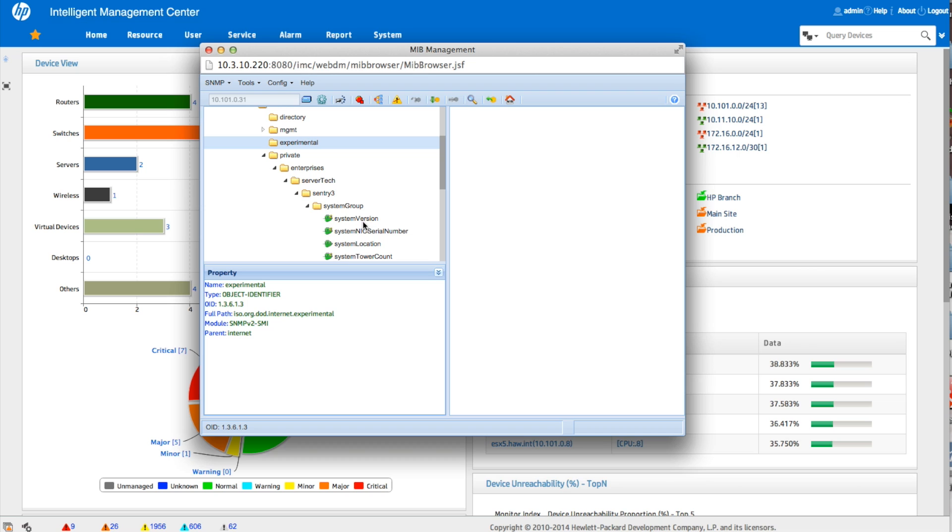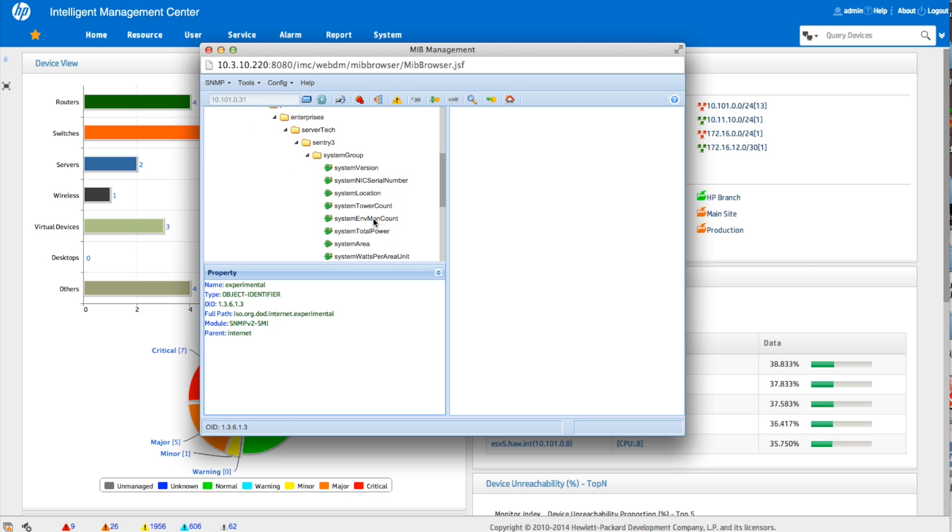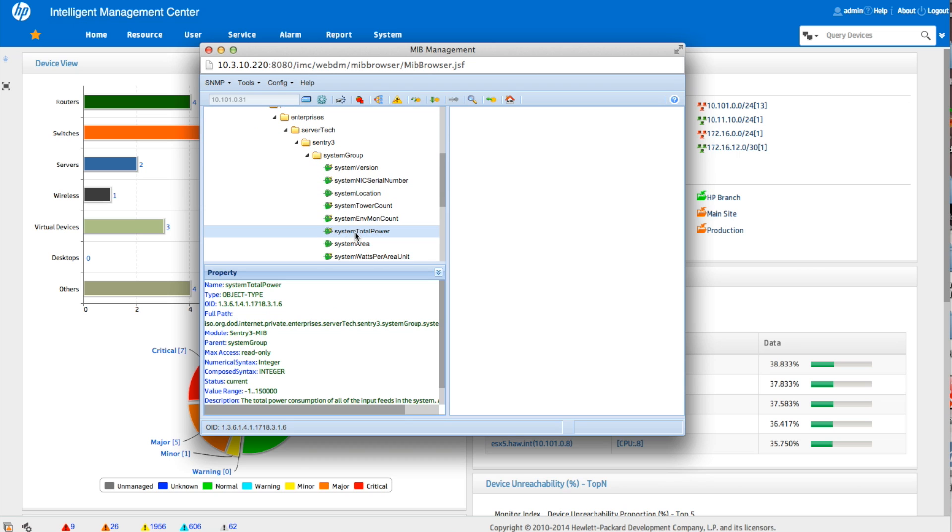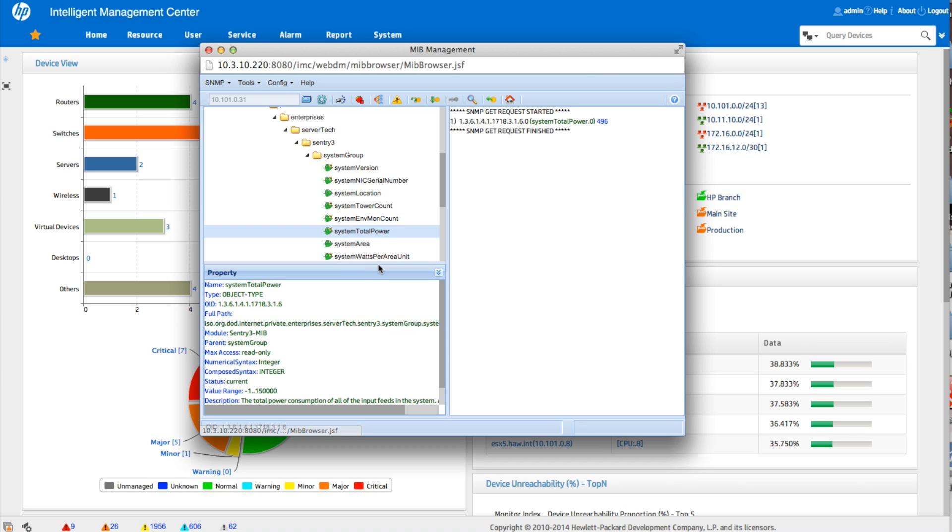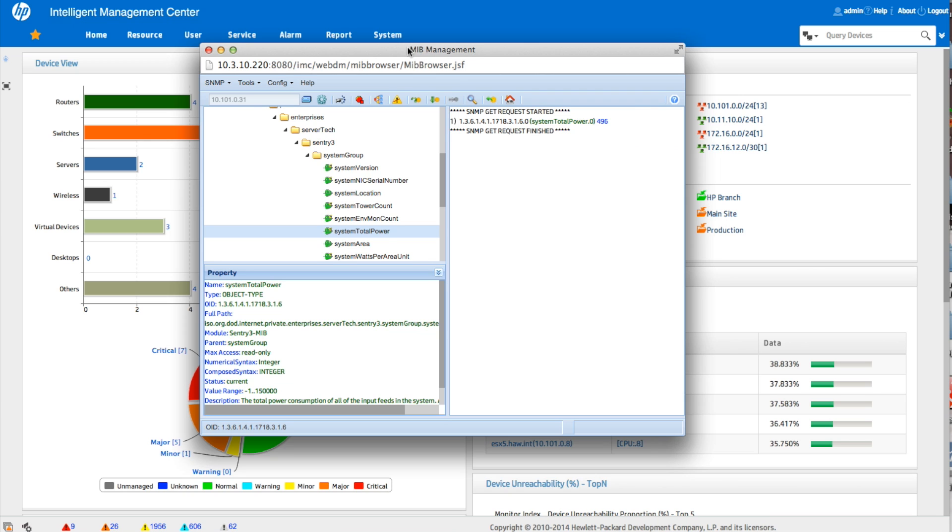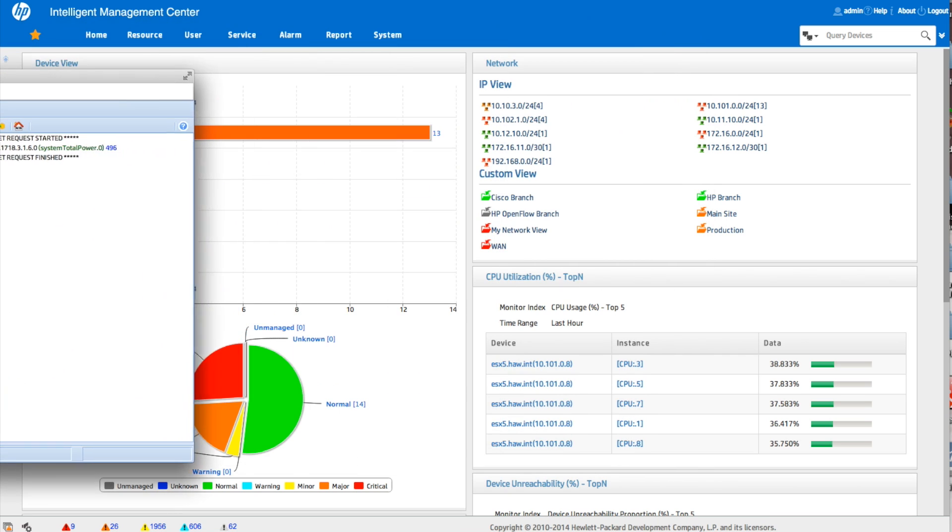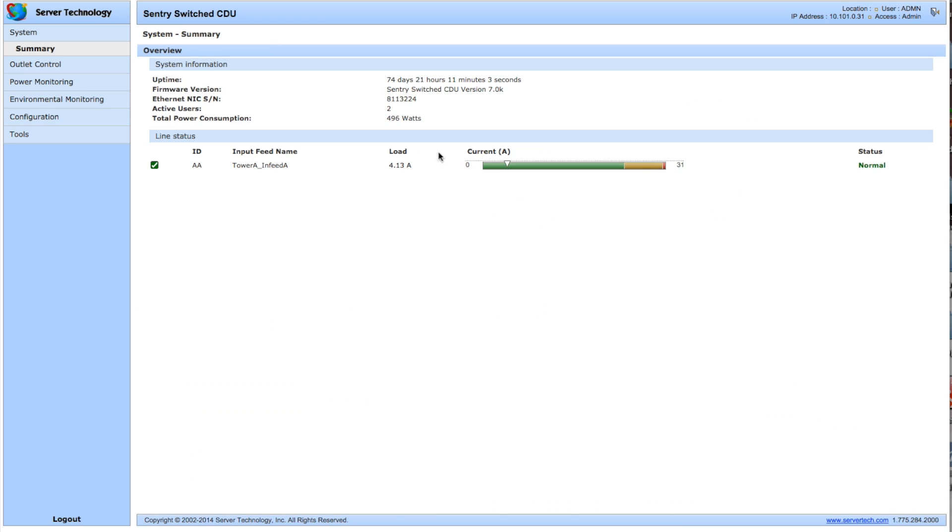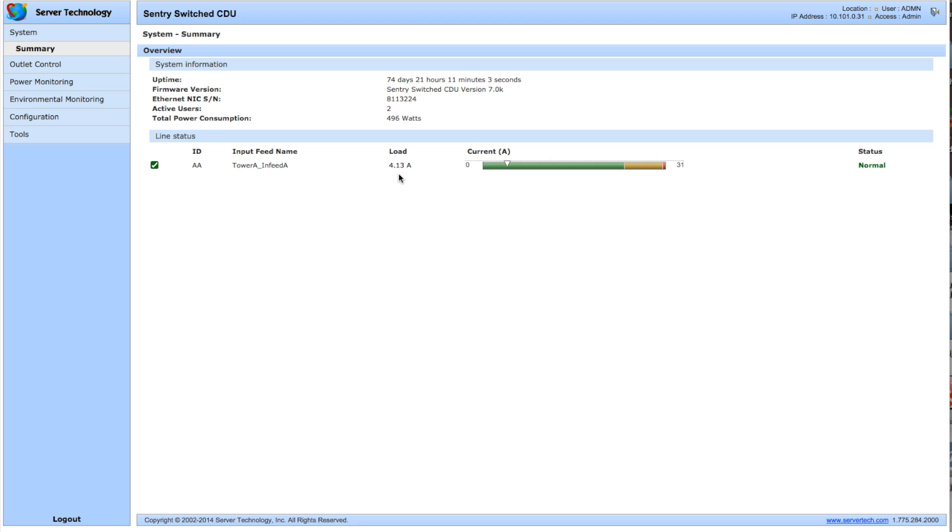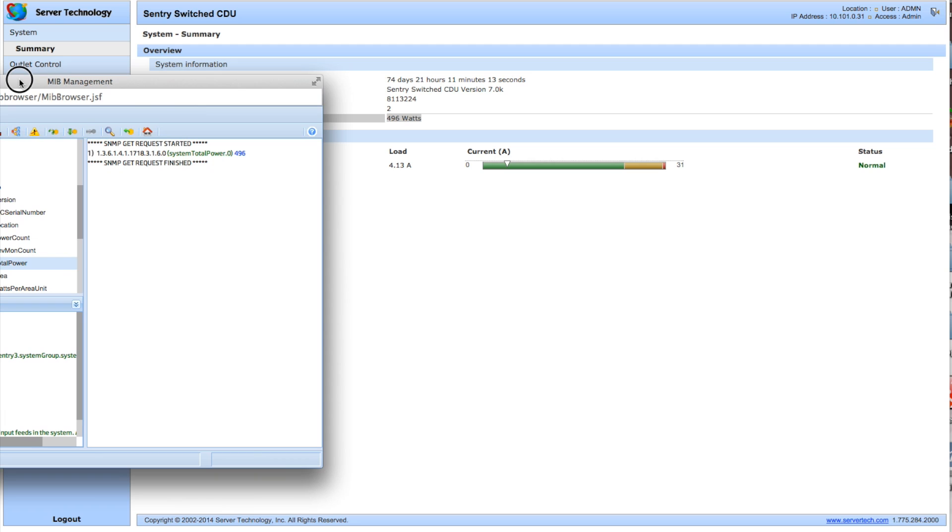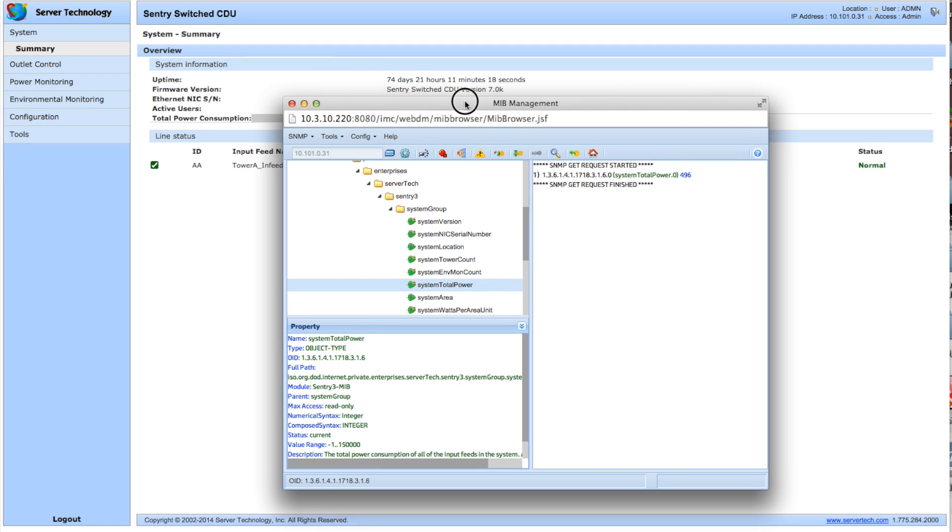So that was in the system group and we're going to go not system total count, system total power. We're going to right click. We're going to go get. Look at that, 496. So that's the exact same number. If we go back over to the sentry, not the load, there we are up here, the 496 watts total power consumption. So this looks like this is indeed the specific MIB object that we want to grab.